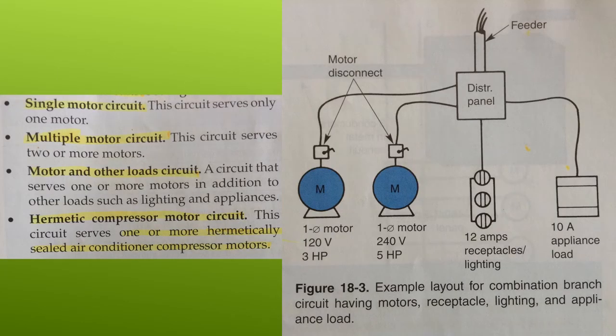Protection of motor feeder conductors. The protection of motor feeder conductors rests primarily on the type of motor circuit involved. For practical purposes, there are four common motor circuits. Single motor circuit, as you can see on the screen, this circuit serves only one motor. Multiple motor circuit, this circuit serves two or more motors. Motors or motor and other load circuit, a circuit that serves one or more motors in addition to other loads such as lighting and appliances. And hermetic compressor motor circuit, this circuit serves one or more hermetically sealed air conditioner compressor motors.